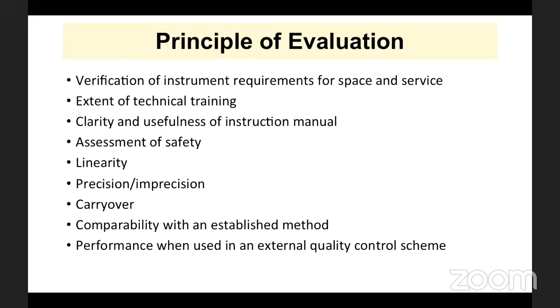You have to see that the machine shall not have significant carryover which affects the decision taken based on that result. Then comparability with an established method. And if you are participating in EQAS, what is the performance of that machine in the EQAS? Previously, we discussed diagnostic sensitivity, diagnostic specificity, positive predictive value, negative predictive value. Now we are talking about analytical sensitivity. What is this? This is the minimum difference which you can get in analytical measurement in a particular machine.